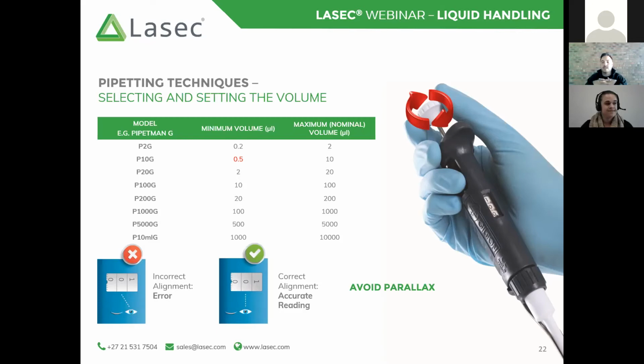Where individuals might struggle is figuring out exactly what that working range is. So from an industry standard, a good rule of thumb is that a pipette can be used to 1/10 of its maximum volume. For example, if I was using a 1000 microliter pipette, I can safely assume that the minimum volume is going to be 100 microliters. If you are confused or not very good with percentages, for pipettes it's quite easy. You just remove the 0 at the end of the maximum volume, and there you have the minimum volume that it can be used for.